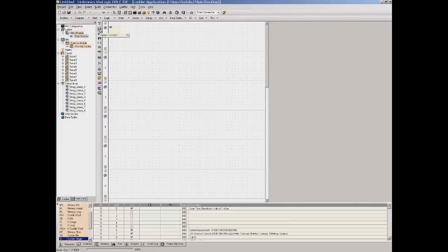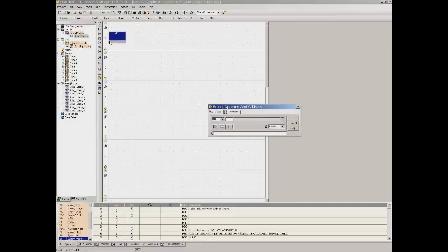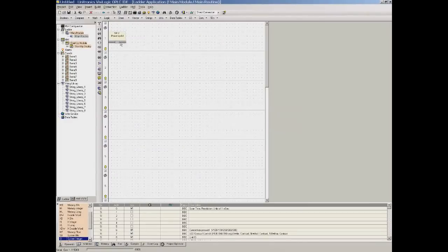I'll grab a direct contact and I'll place that down inside net 1. Now what I'm going to use here is a standard procedure for Unitronics, again covered in our Ethernet webinar. I'll use a system bit 2, which is a one-time power-up bit. So I'll reiterate as well, whenever you're using Ethernet, you need to have the different configuration parameters defined off a single one-shot condition. So a system bit 2 power-up bit is going to be high for a single scan only in the program. The first time the controller is powered up or it's reset, system bit 2 will be active. So that's why I'm going to use system bit 2 for essentially any of my communications configuration parameters here.